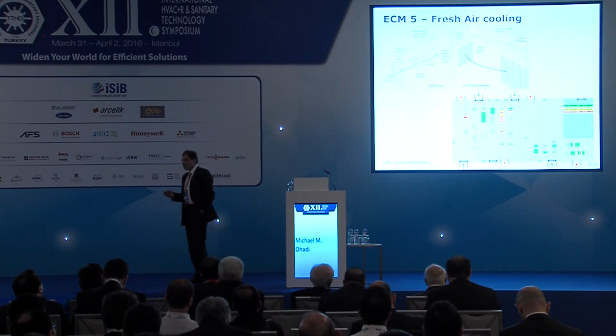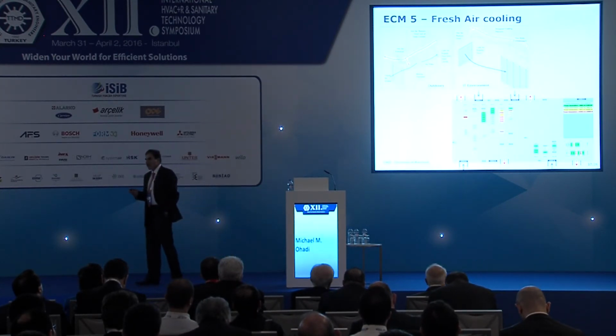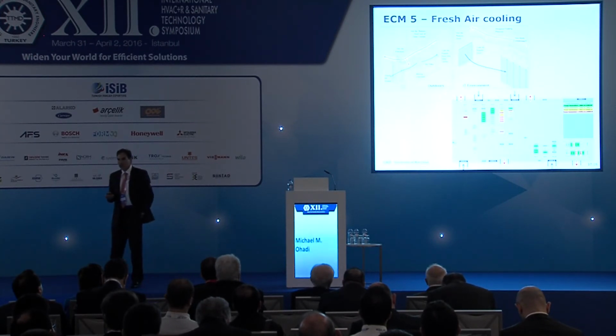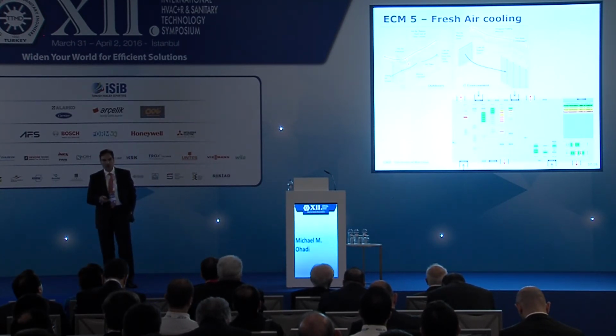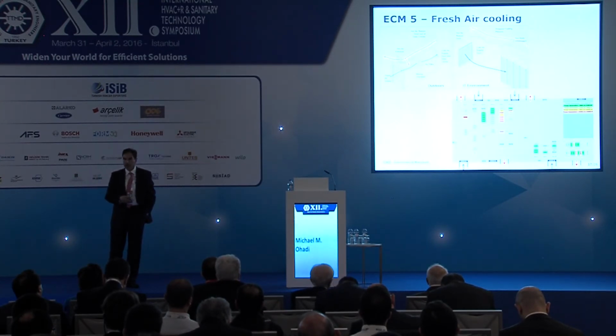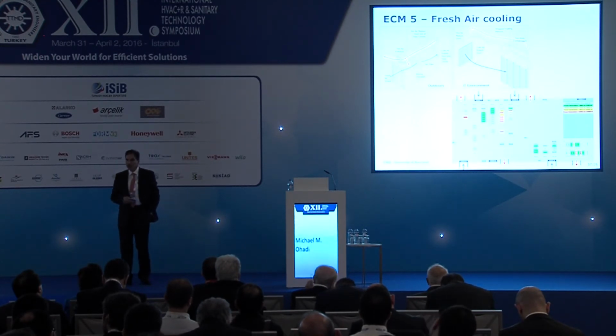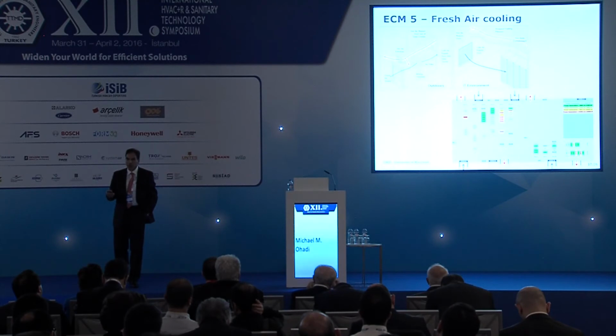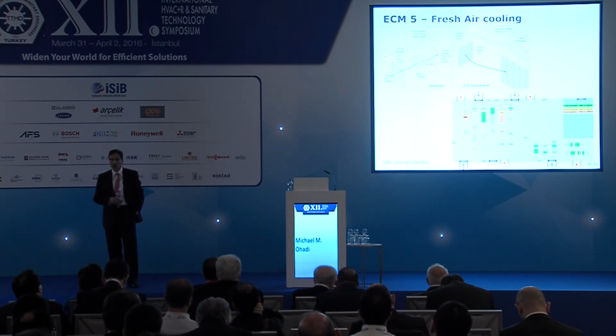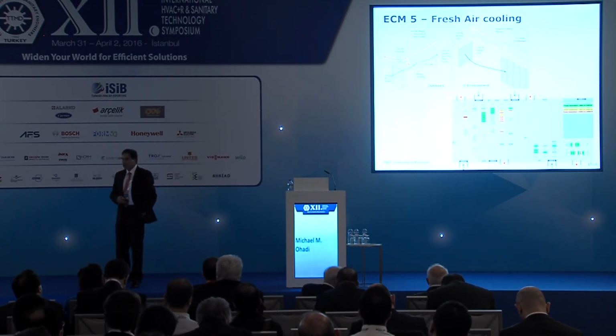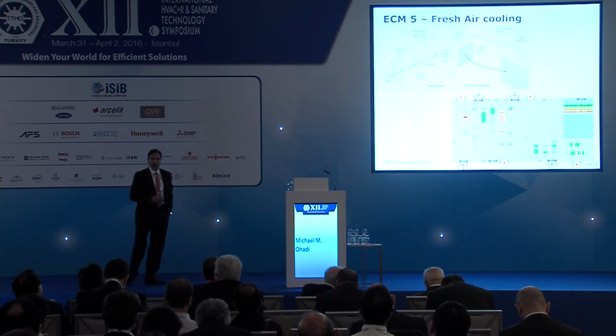People have questioned the problem with humidity. ASHRAE conducted a research project recently and found you could actually vary humidity greatly, from as low as a few percent to as high as 90%, and your electronics would be safe. This is a very new finding, probably a year old. I go regularly to TC 9.9, and there are publications from ASHRAE you could look up. So fresh air cooling is becoming more and more attractive.